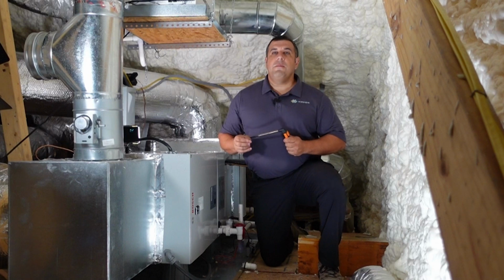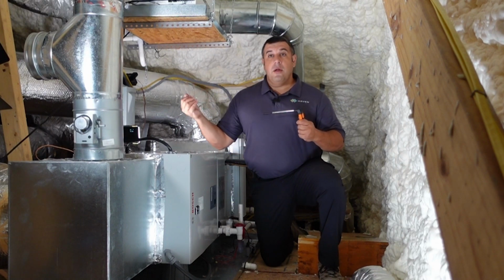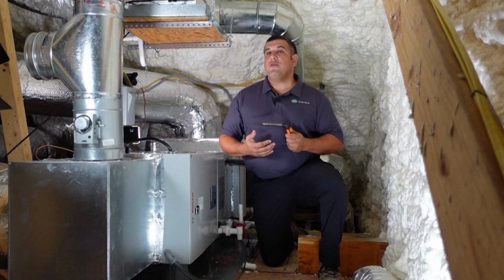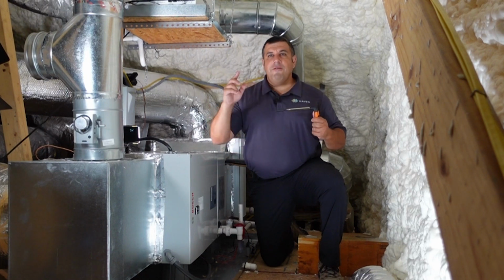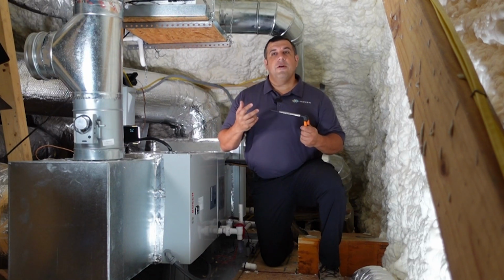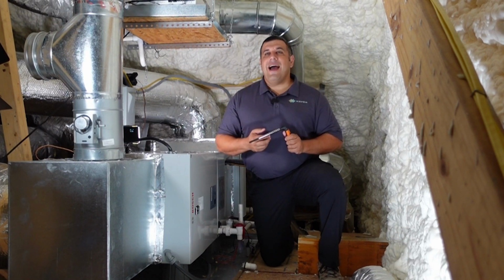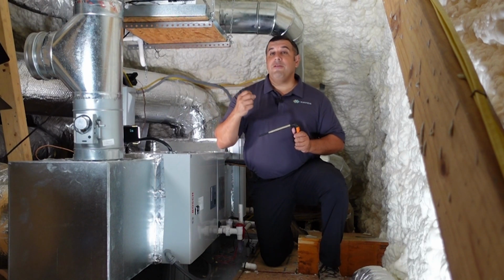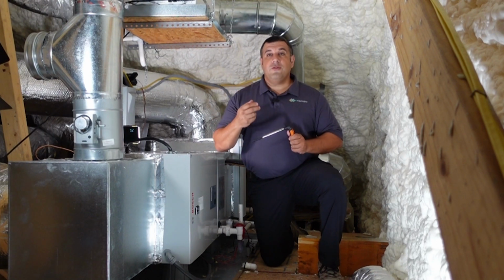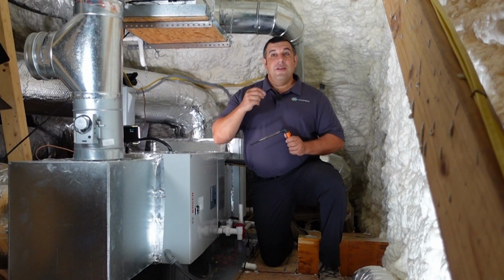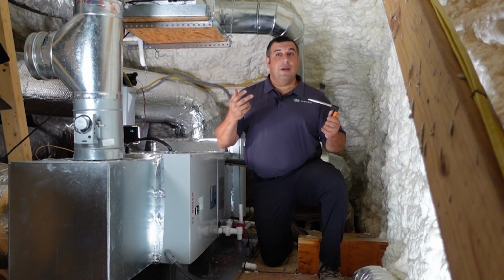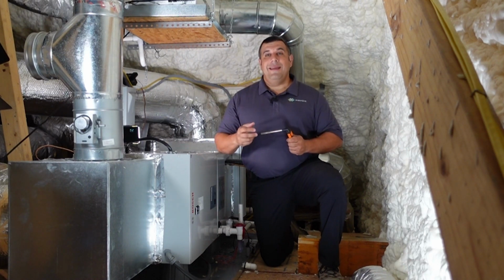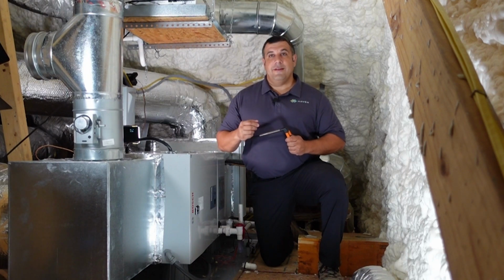This is especially important when a home has multiple smaller ducts converging together in its central plenum, as these sections often have uneven and turbulent airflow. Luckily, the Haven IAQ app also has an airflow validation tool that I'll demonstrate in the install video. This should be performed when the system is running at its lowest operating speed to test its minimum flow velocity.